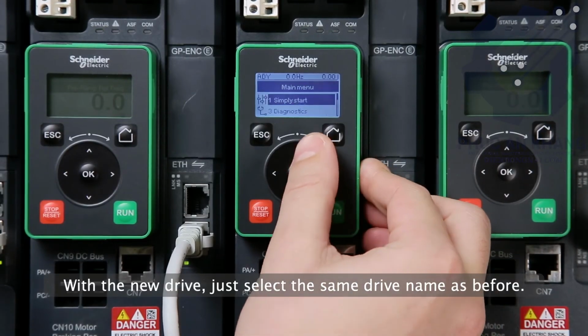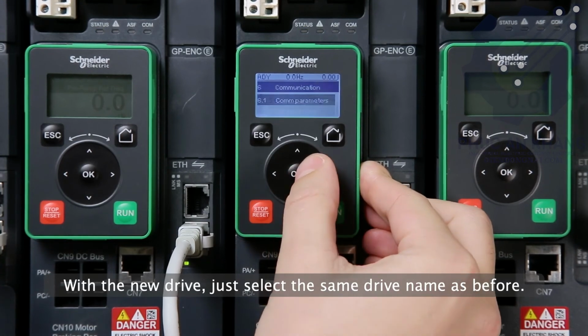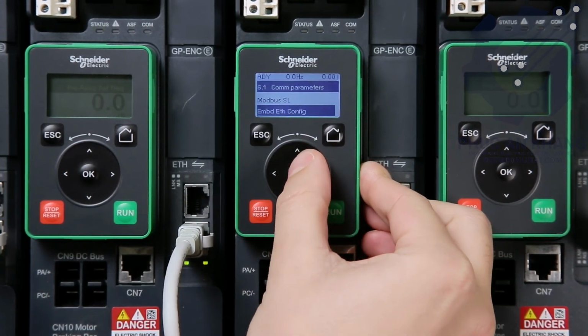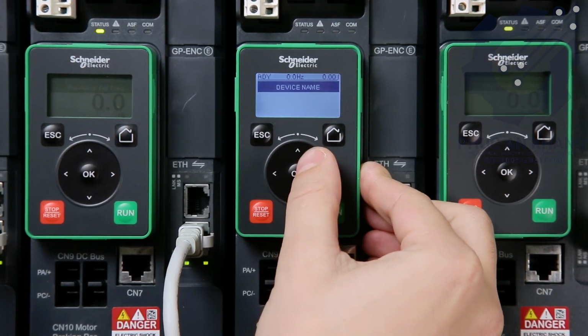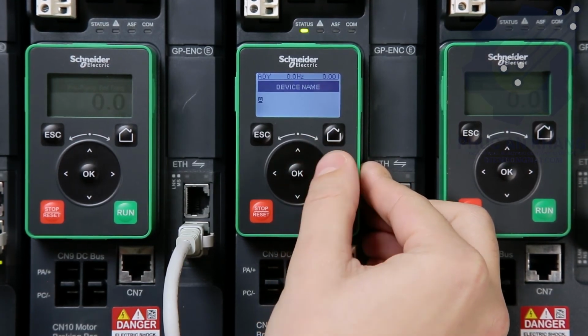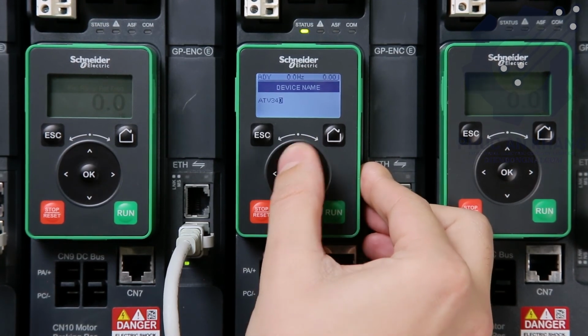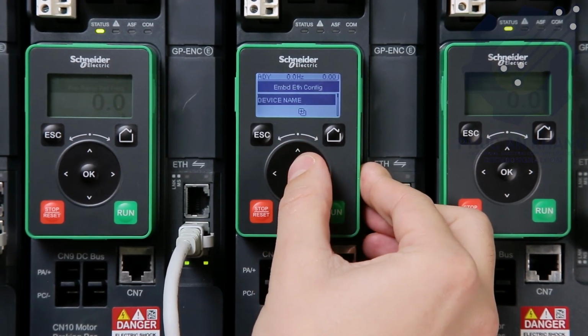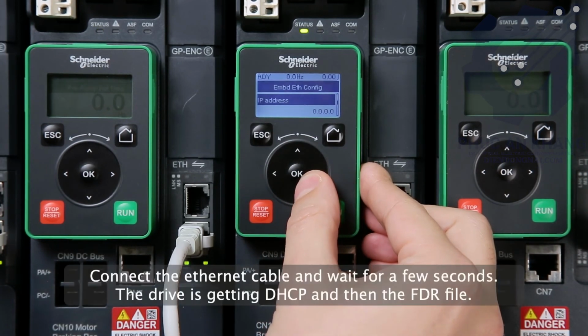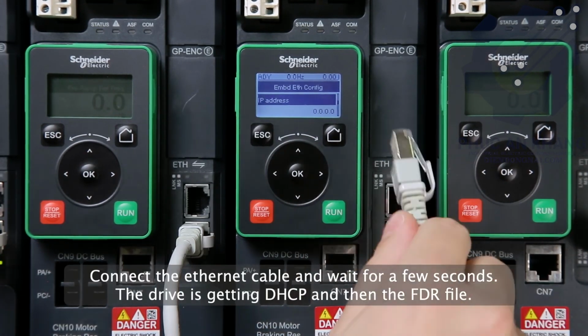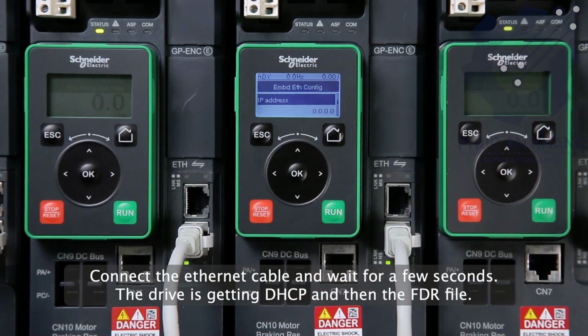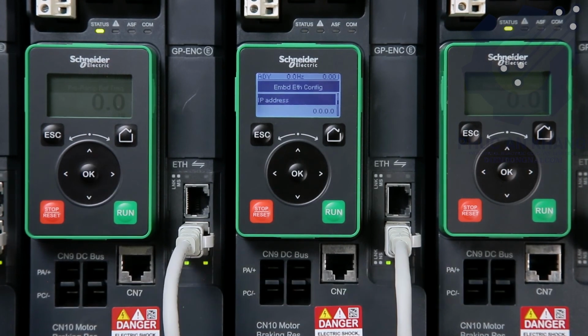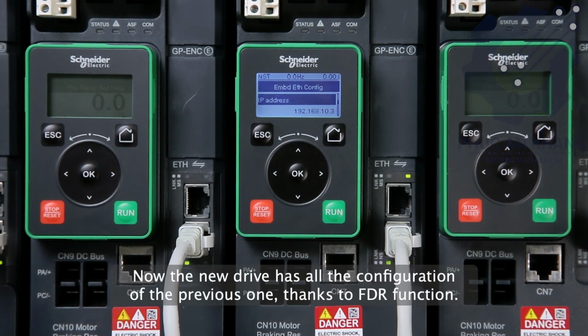With the new drive, just select the same drive name as before. Connect the Ethernet cable and wait for a few seconds. The drive is getting DHCP and then the FDR file. Now, the new drive has all the configuration of the previous one, thanks to FDR function.